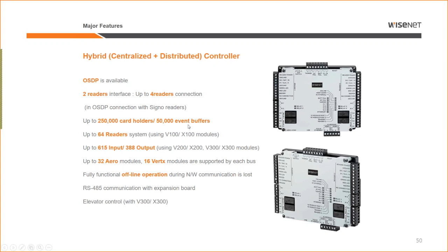What is a subcontroller? This one, X100, is a subcontroller. Each subcontroller can connect to 2 readers, so 32 into 2 is 64. That's why it says here 64 readers using X100 module, 32 boards. You don't have to worry about all this. The controller itself can hold the data. That's why I said even if the TCP connection is lost, it knows who the card holder is. It will keep in its memory all the events, access granted and denied, up to 50,000 events. After that, you have to connect the TCP, so all will be pushed to the database.